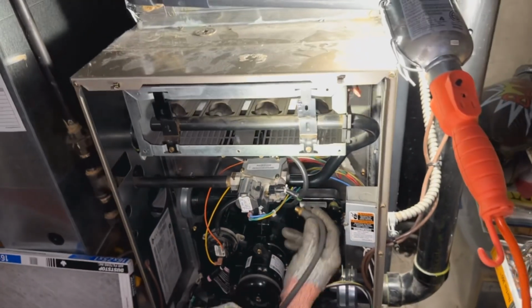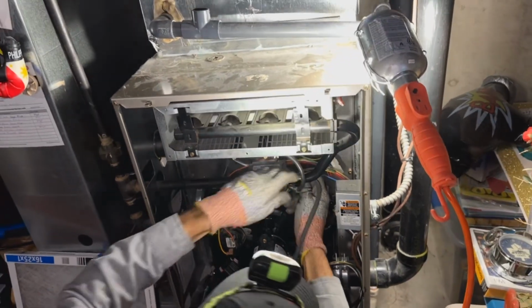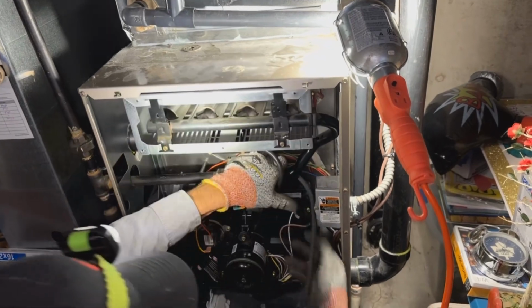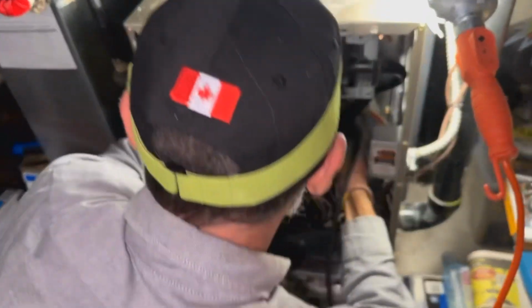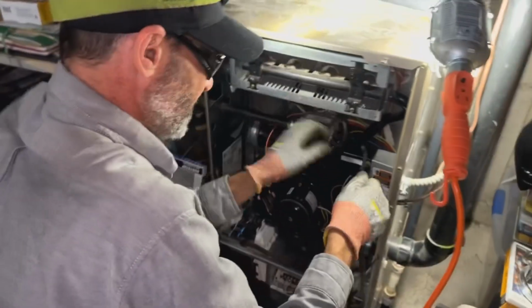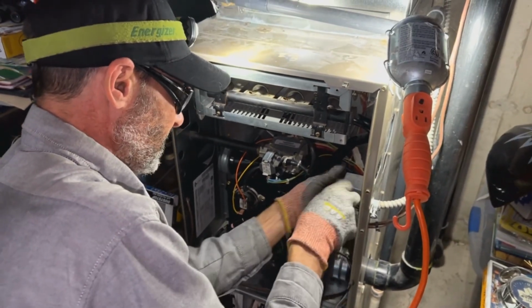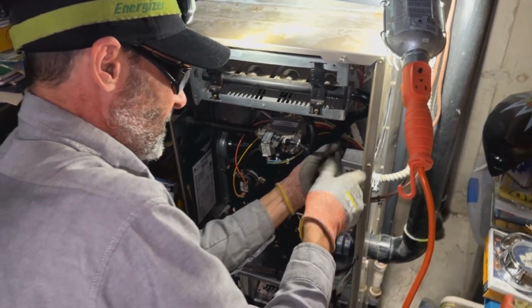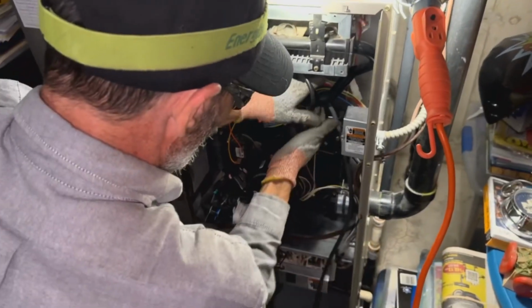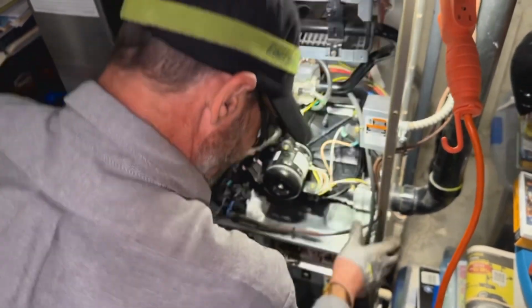So just like me, Paul's taking the door off. We're going to fire this back up and see what the gas pressure holds steady at. Because when I was doing it earlier, ladies and gentlemen, my gas pressure was all over the place, so I don't know if it was my meter or if my gas valve's acting up. We're just going to confirm it and then change the gas valve if we need to.